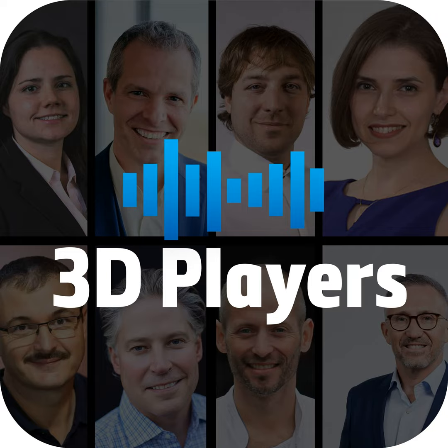The machines are more complicated. The safety measures surrounding it are more complicated. The pre and post processing steps needed are definitely more complicated. Think of what you need for a metal 3D printed part: stress relieving, different types of heat treatments, things like hipping, and then further machining of components, which many 3D printed implants get after they're printed, for mating tolerances and whatnot. All that to say, it's not a little thing. For a hospital to get involved and say, we want to do metal 3D printing, they've got to have a really good reason to do it and know that it's probably a multi-million-dollar commitment.